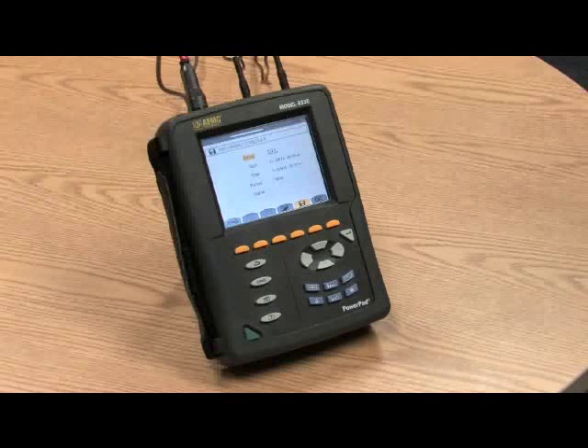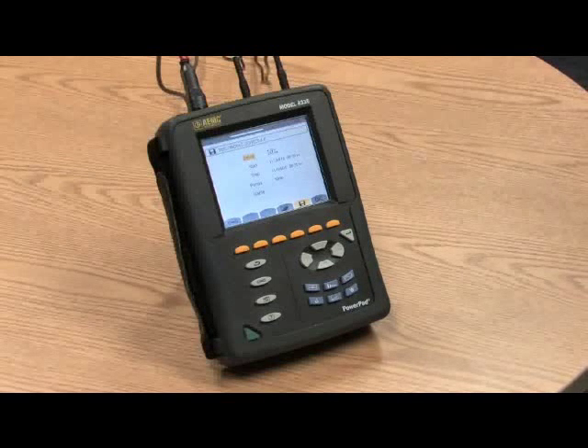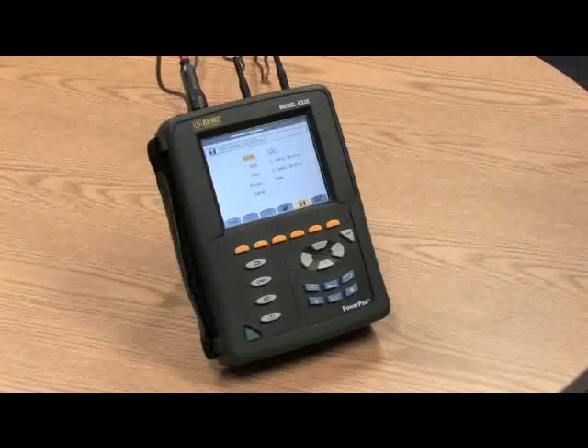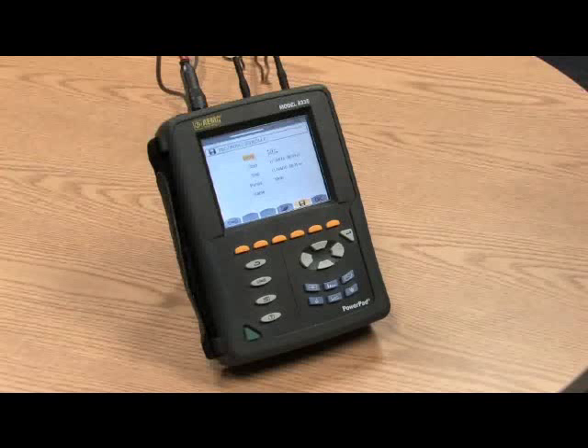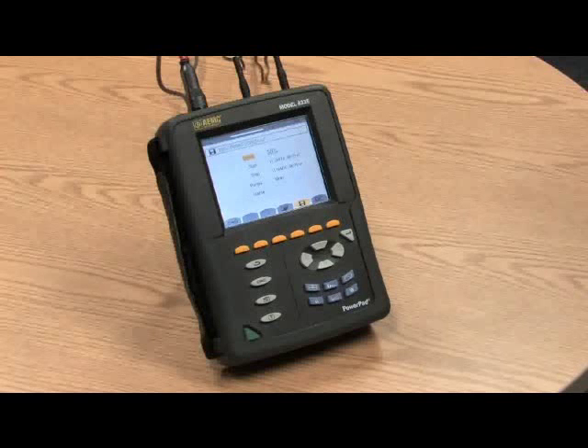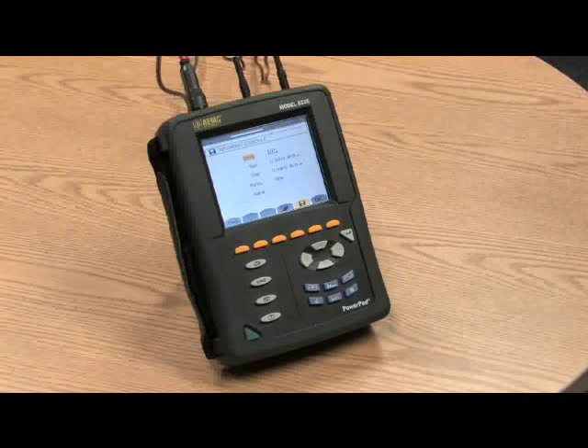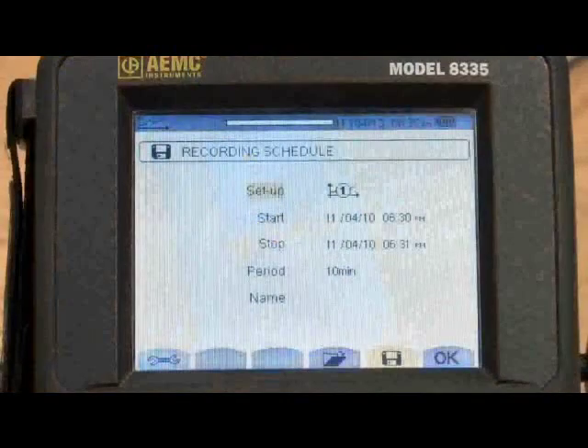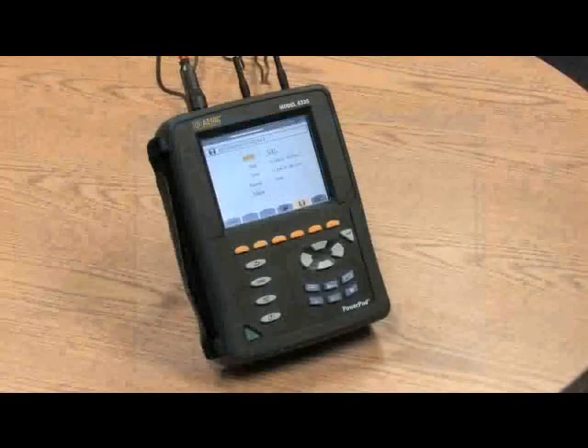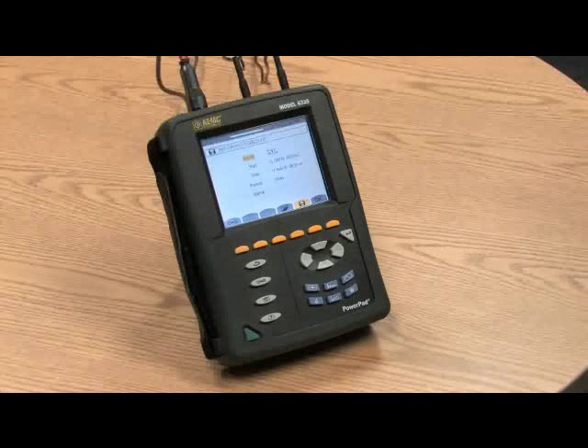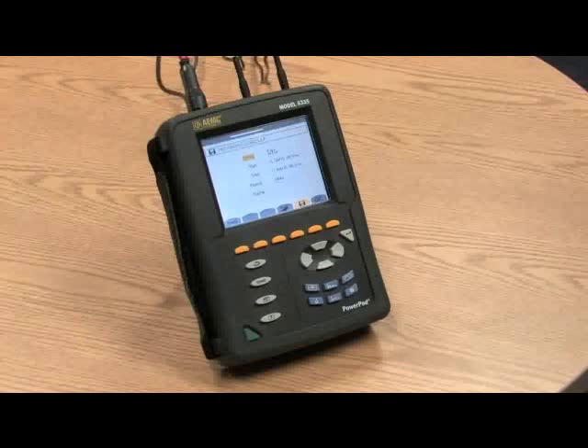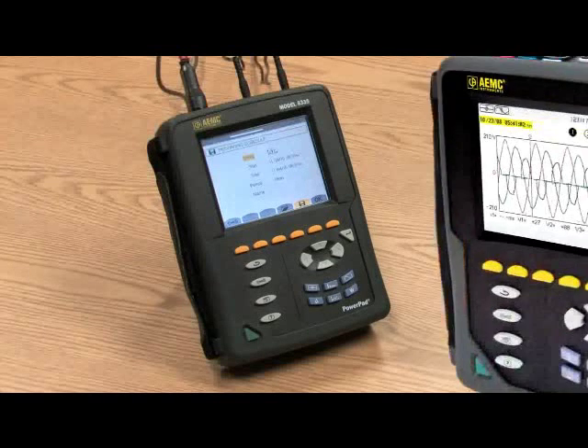The unit is powered by a 9.6 volt nickel metal hydride rechargeable battery, and it has an external charger. And we'll talk about how that's connected in a little bit. Fully charged battery with the display on will run about eight hours. With the display off and recording, it'll run for about 35 hours on the battery. Of course, it can run indefinitely plugged into the charger.